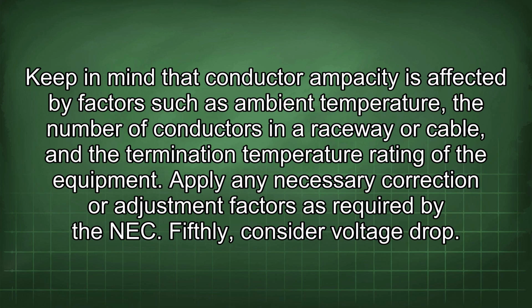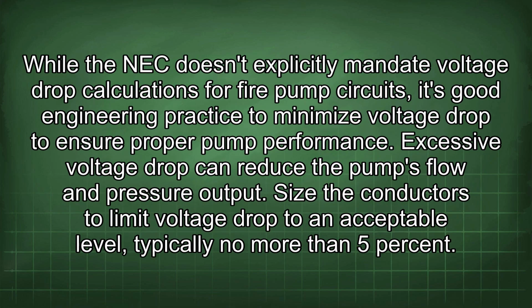Fifthly, consider voltage drop. While the NEC doesn't explicitly mandate voltage drop calculations for fire pump circuits, it's good engineering practice to minimize voltage drop to ensure proper pump performance. Excessive voltage drop can reduce the pump's flow and pressure output. Size the conductors to limit voltage drop to an acceptable level, typically no more than 5%.